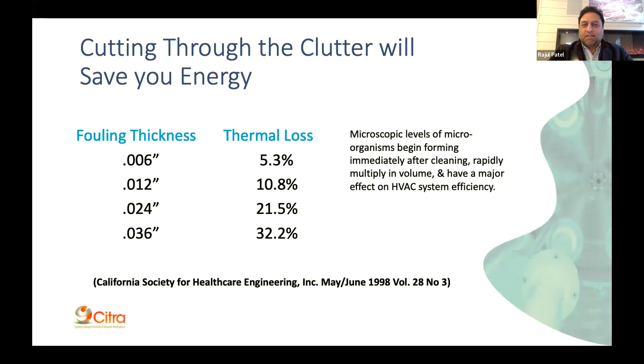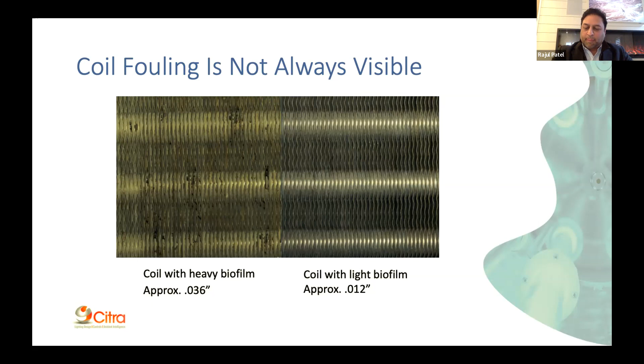And it's not always visible. Many times when we open up these units and look at them with the HVAC techs at a given facility, they may say they manually clean their coils and they visibly look fairly clean. But we're looking at a microscopic level of biofilm, so it's not always clearly visible, though the negative effects are there. It varies unit to unit, even in the same building, how much biofilm is built up.